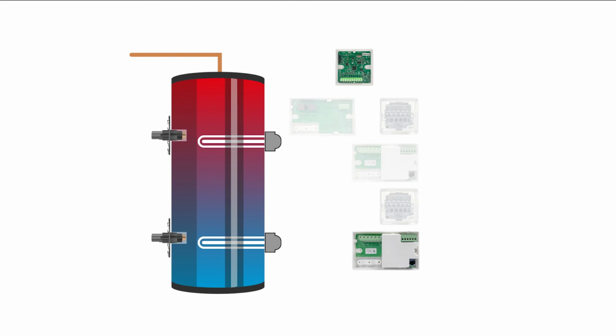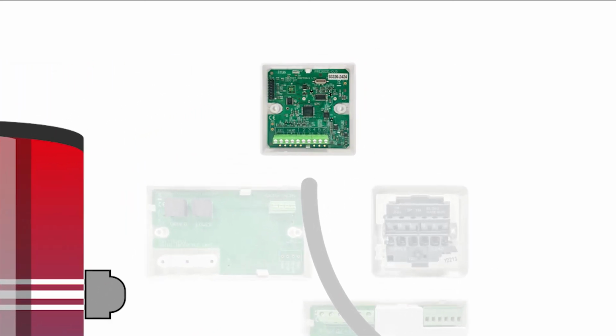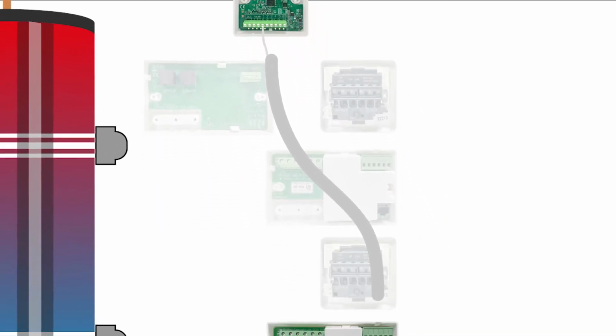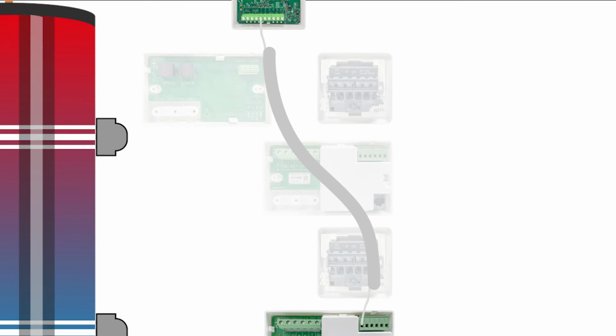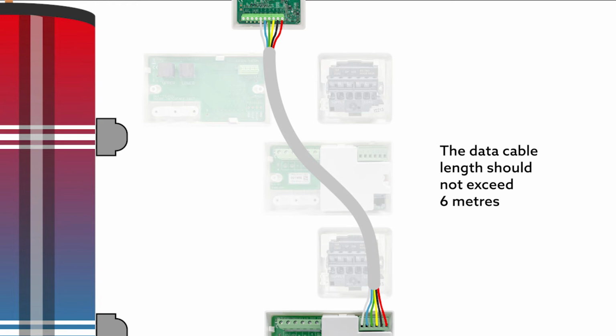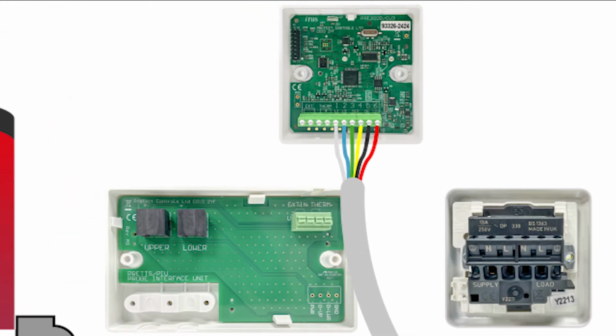Using a standard 6-core low-voltage alarm cable, connect the control unit to the power unit, ensuring the coloured wires going to the terminals match. White wire from terminal 1 on the control unit to terminal 1 on the power unit, blue terminal 2 to 2, green 3, yellow 4, black 5 and red 6. The length of the data cable should not exceed 6 meters. Do not use a solid core data cable. Ensure all terminals are secure, but do not over-tighten.